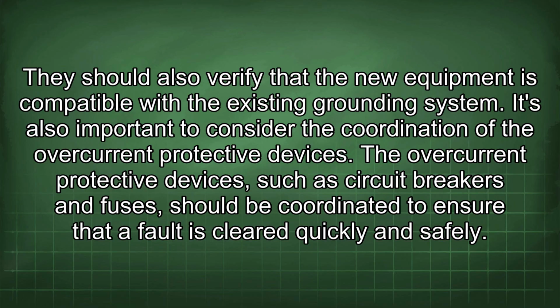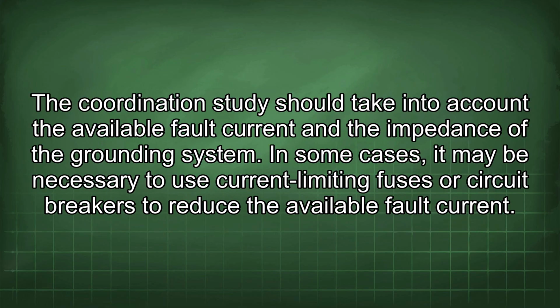It's also important to consider the coordination of the overcurrent protective devices. The overcurrent protective devices, such as circuit breakers and fuses, should be coordinated to ensure that a fault is cleared quickly and safely. The coordination study should take into account the available fault current and the impedance of the grounding system. In some cases, it may be necessary to use current-limiting fuses or circuit breakers to reduce the available fault current.